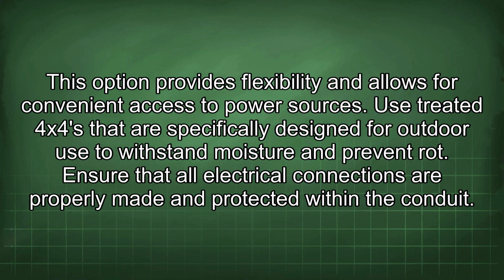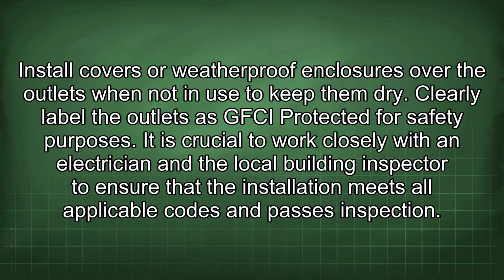Use treated lumber that is specifically designed for outdoor use to withstand moisture and prevent rot. Ensure that all electrical connections are properly made and protected within the conduit. Install covers or weatherproof enclosures over the outlets when not in use to keep them dry. Clearly label the outlets as GFCI protected for safety purposes.